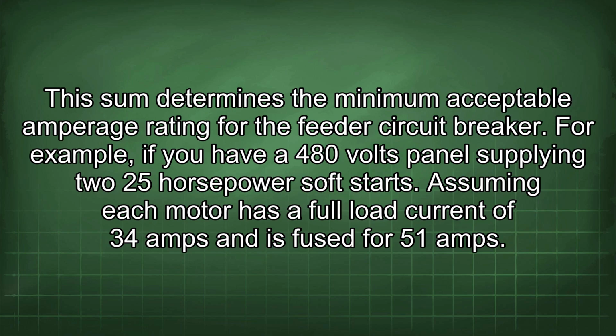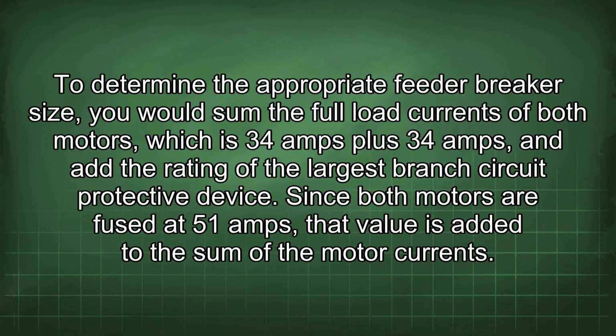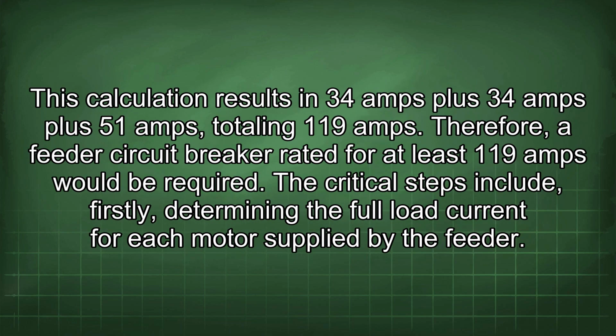For example, if you have a 480 volt panel supplying two 25 horsepower soft starts, assuming each motor has a full load current of 34 amps and is fused for 51 amps. To determine the appropriate feeder breaker size, you would sum the full load currents of both motors, which is 34 amps plus 34 amps, and add the rating of the largest branch circuit protective device. Since both motors are fused at 51 amps, that value is added to the sum of the motor currents. This calculation results in 34 amps plus 34 amps plus 51 amps, totaling 119 amps. Therefore, a feeder circuit breaker rated for at least 119 amps would be required.